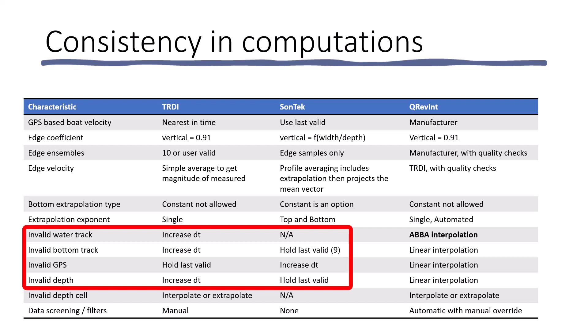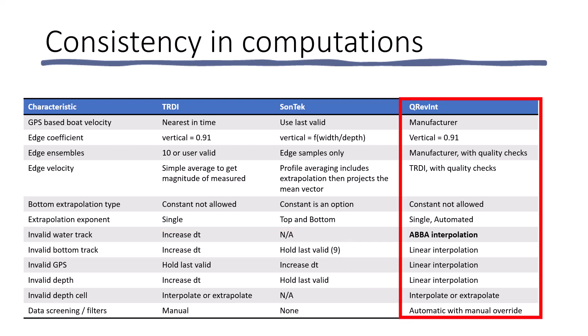If the boat velocity was computed with GPS, TRDI, instead of increasing DT as they had for water track and bottom track, they would hold the last valid GPS velocity until the next valid GPS velocity was obtained. Conversely, Sontek, with bottom track, they were holding the last valid, if it was from GPS, they would increase delta t. So, you can see that neither manufacturer was consistent with their own software, and in fact, they did almost the exact opposite of what the other manufacturer did in the same situation. So, the idea with QREVINT was to provide a consistent set of computational algorithms, so that you would get the same discharge, no matter if you collected the data with a TRDI instrument or a Sontek instrument.